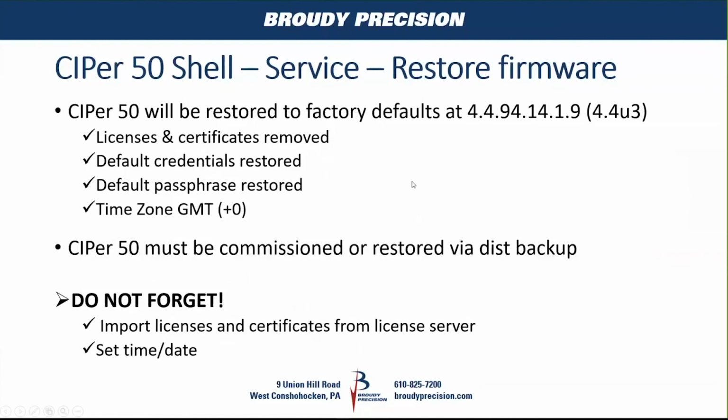So when you do that, all the licenses that have been imported, certificates that have been imported, they get blown away. The default credentials get used, the default passphrase gets used, and I found late last night the time zone actually goes back to GMT, so it goes back to time zone 0.